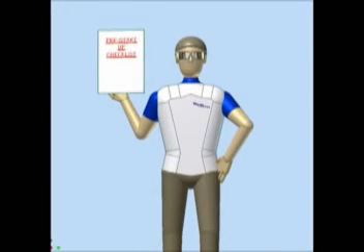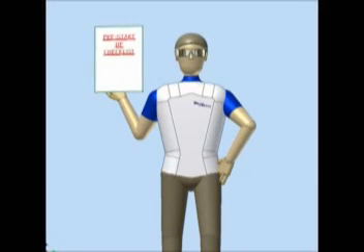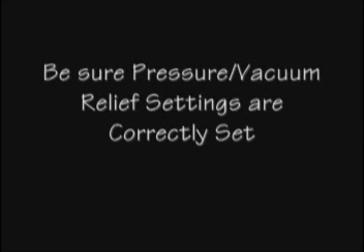Before services are scheduled, a pre-startup checklist will be forwarded to the installing contractor in preparation for the startup. The float test is to ensure the cover travels freely over the entire range of travel without binding and that the operating and relief pressures are properly set with the correct weights as specified.